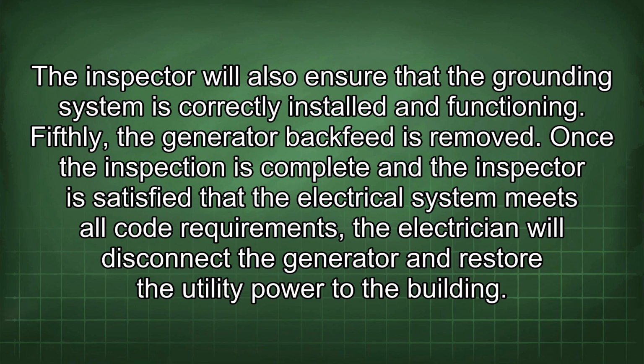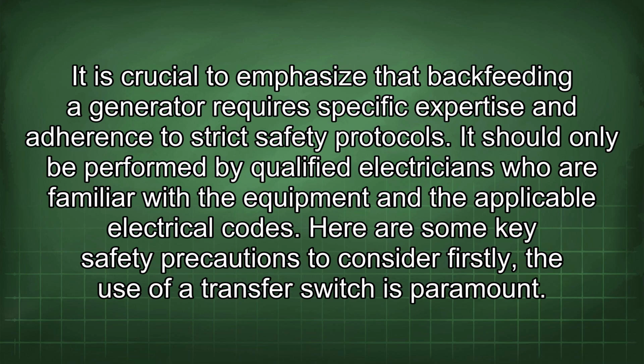Fifthly, the generator backfeed is removed. Once the inspection is complete and the inspector is satisfied that the electrical system meets all code requirements, the electrician will disconnect the generator and restore the utility power to the building. It is crucial to emphasize that backfeeding a generator requires specific expertise and adherence to strict safety protocols. It should only be performed by qualified electricians who are familiar with the equipment and the applicable electrical codes. Here are some key safety precautions to consider.